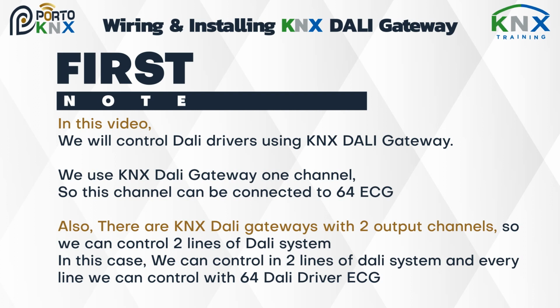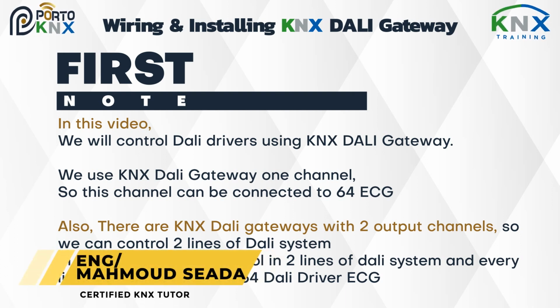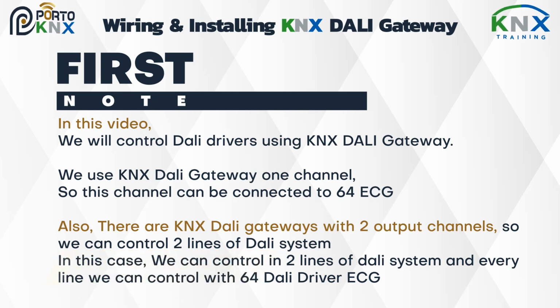In this video, we will control DALI drivers using KNX DALI gateway. We will use KNX DALI gateway 1 channel, so this channel can be connected to 64 ECG. Also, there are KNX DALI gateways with 2 output channels, so we can control 2 lines of DALI system. In this case, every line we can control with 64 DALI driver ECG.